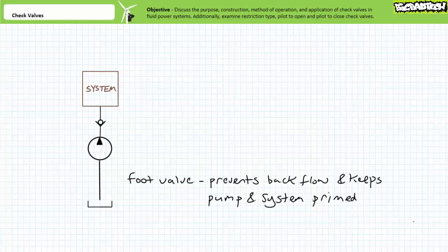Alternatively, the check valve could be relocated onto the output of the pump and to the input of the system. This check valve's orientation allows the pump to provide pressurized flow to the system. However, when the pump is disabled, it prevents backflow from the system, thereby keeping the system primed and filled with fluid.